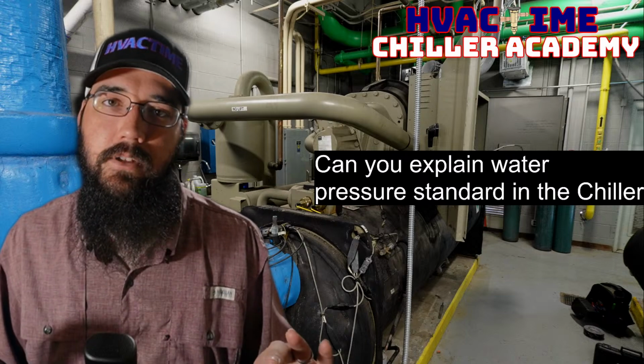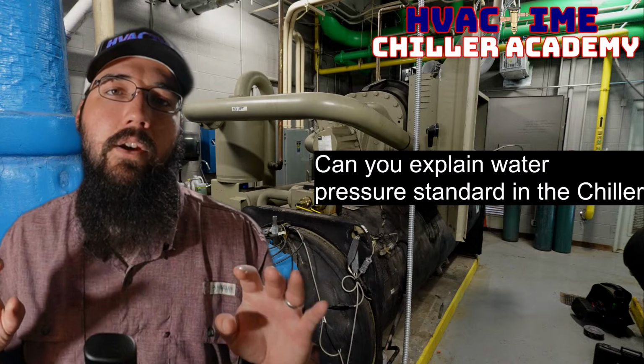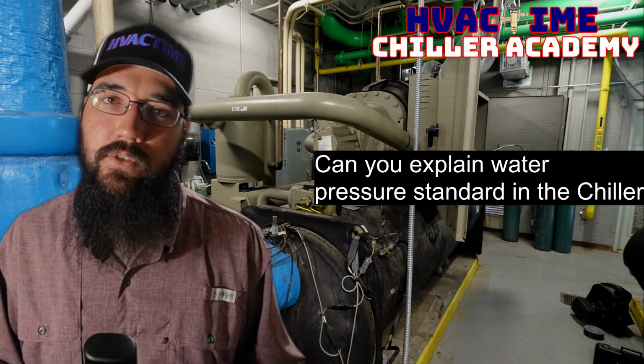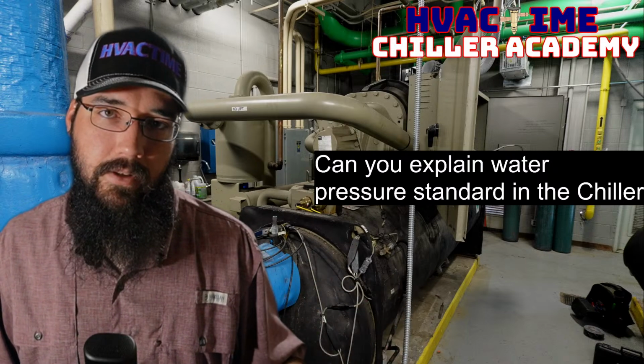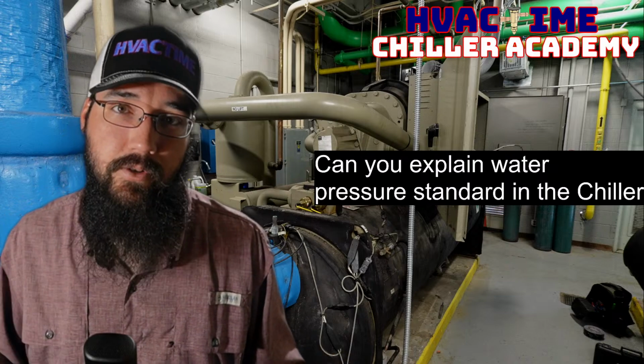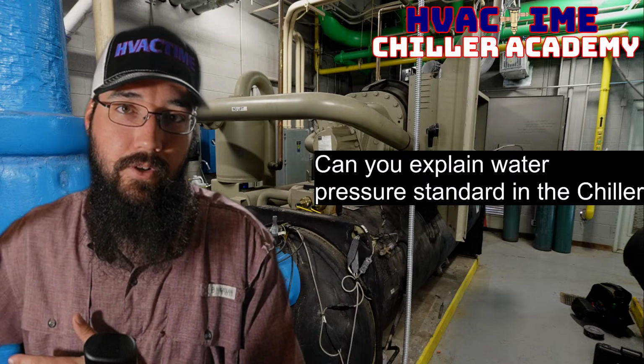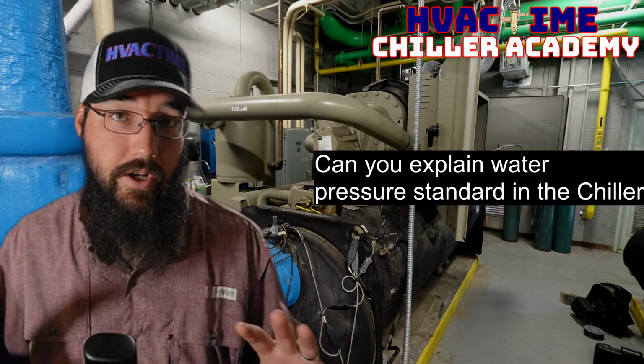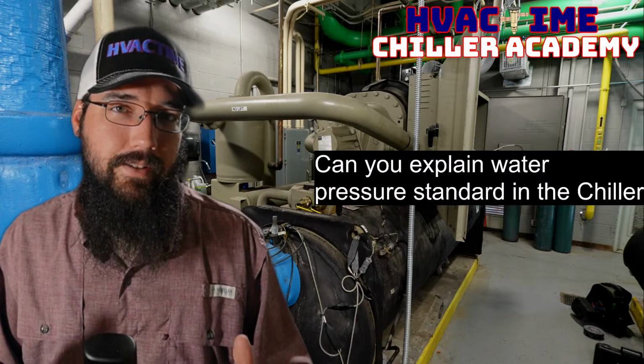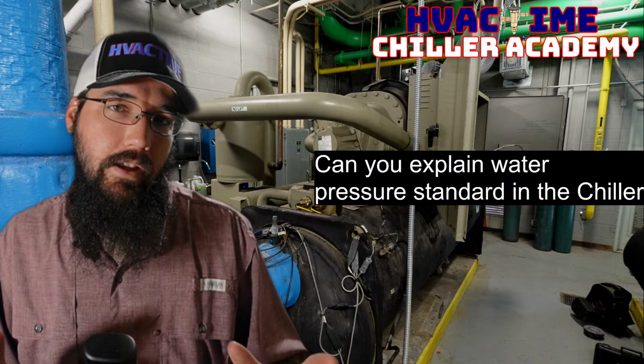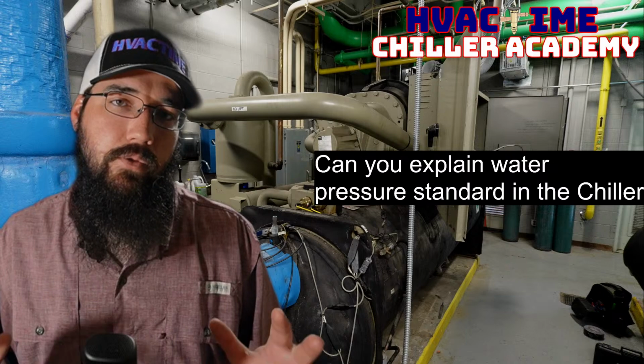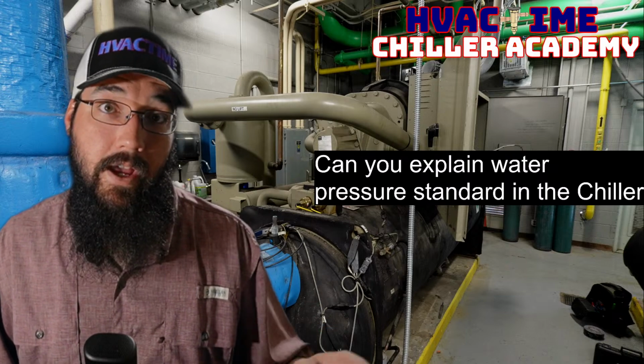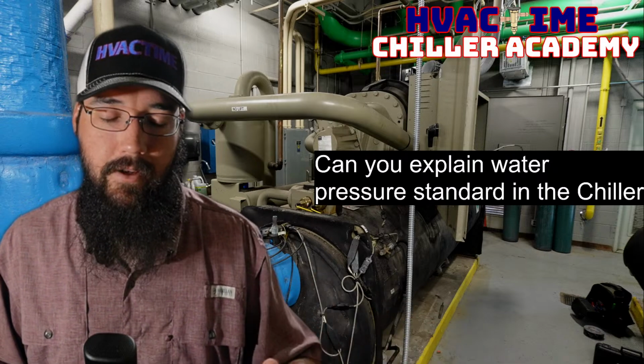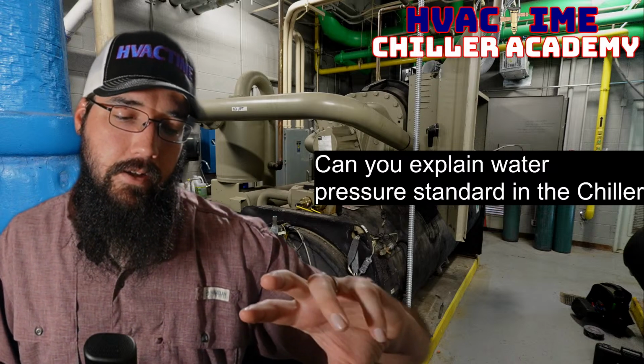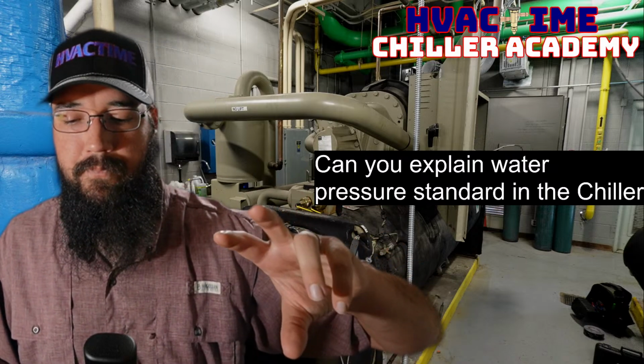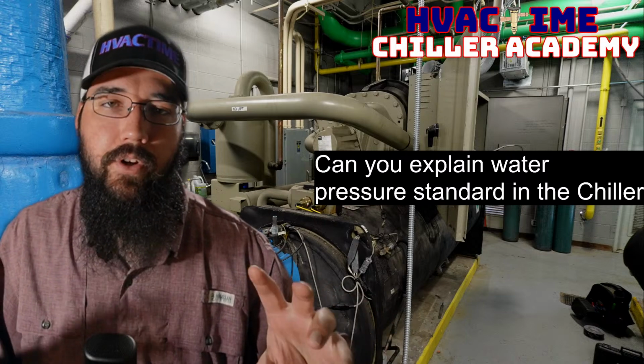I'm going to very carefully say this, because this should not be your default go-to when it comes to trying to determine flow. But in a lot of circumstances, a fairly consistent DP you will have, especially on the smaller tonnages. Now, as this scales to larger equipment, these numbers mean a lot less as you start getting to 200 or 2,000 tons and above, right? It changes a lot. Anyway, 2 to 4 PSID per pass is a get-you-in-the-ballpark type of number. So if you've got a 2-pass machine, one way to know that: do both pipes leave out the same side? Yes, 2-pass, okay? So if that is true, then a 4 to 8 DP would, again, get you in the ballpark.